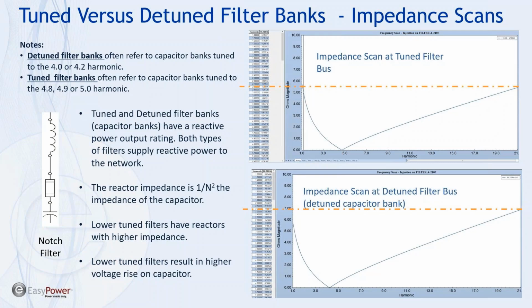So what does that mean? If it's a 4.2 tuned filter, it means we have more impedance associated with the filter branch. It means we have more voltage drop across this component at 60 hertz.